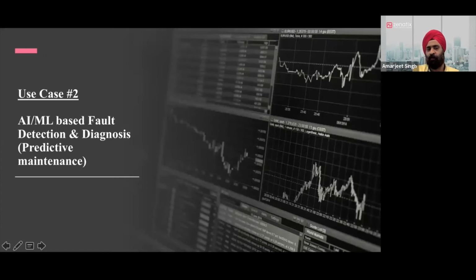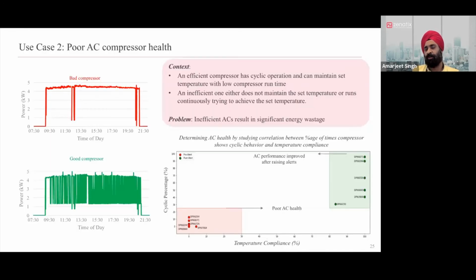The second use case is around fault detection and diagnosis. In a compressor-based air conditioning system, the compressors should show on and off cycles - that's a typical thermodynamic cycle. If your air conditioning isn't giving those on and off cycles, one, it's consuming more power, and two, it's an indicator that something bad is going to happen soon, so you should take action now. By doing such analytics about system health, you can do predictive and preventive maintenance.